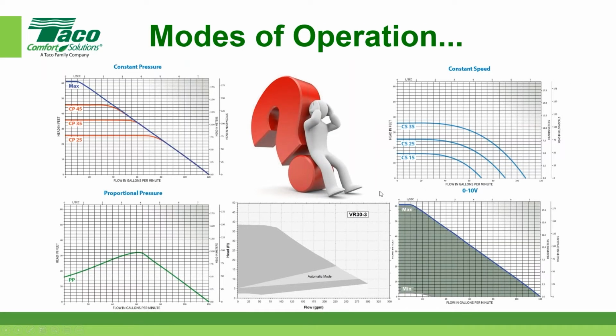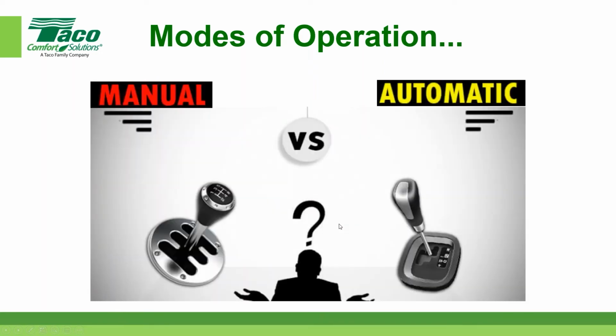Now, what mode do I use? I told you there's up to 5, and I'm showing you the 5 of them here. Constant pressure, fixed speed. I like to change that order because if you use the two constants in a row, you might get confused. So constant pressure, fixed speed, proportional pressure, 0 to 10, or these adaptable auto modes. We'll get into all of these and make sure you feel comfortable about them.